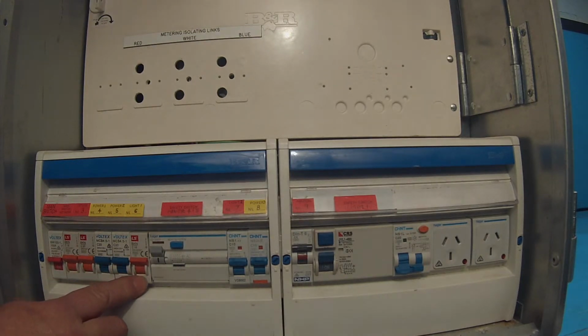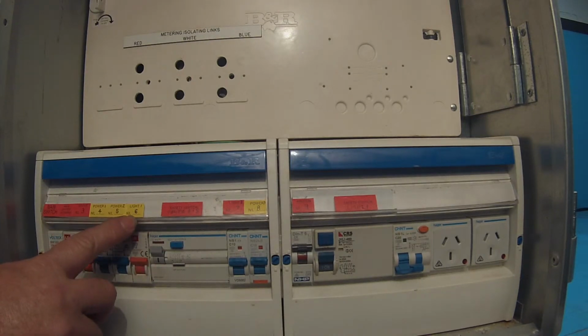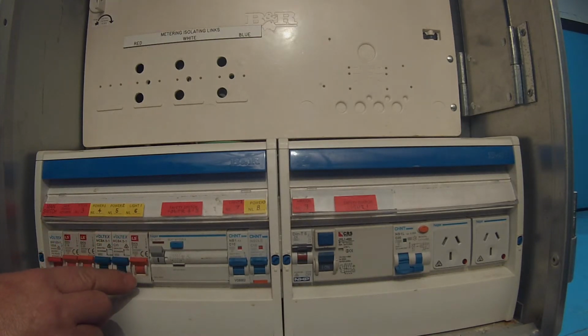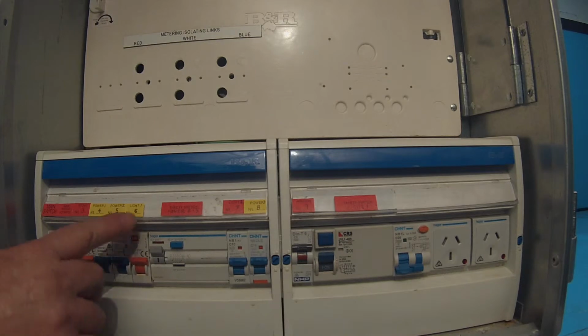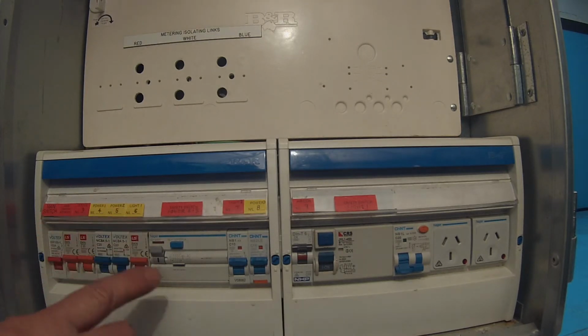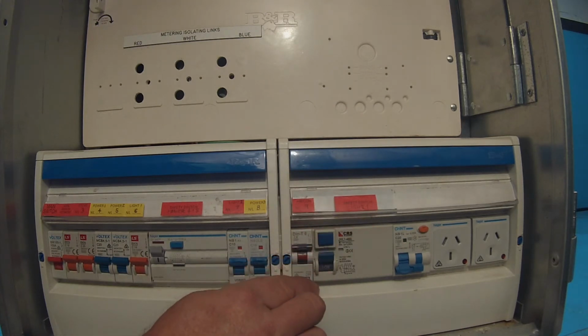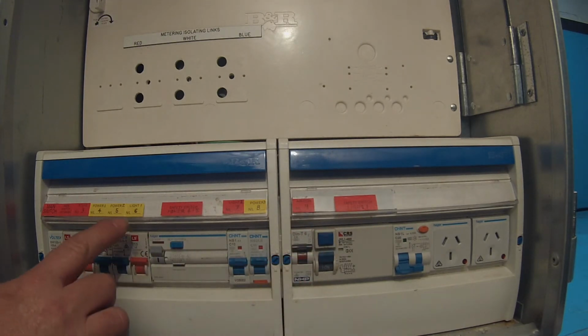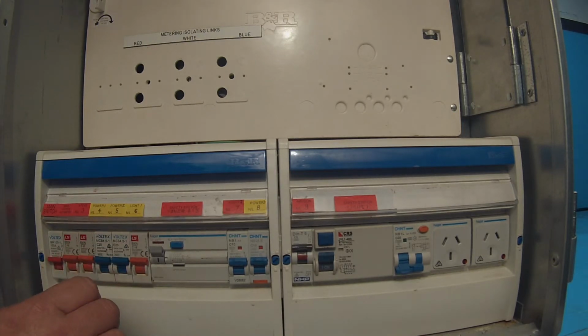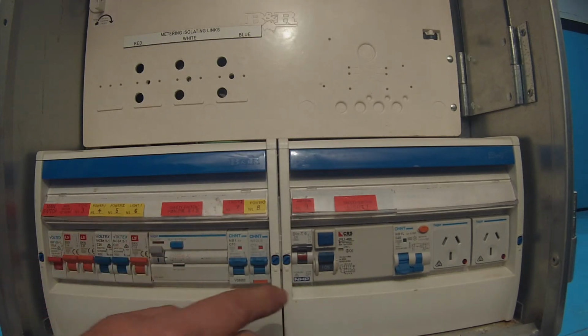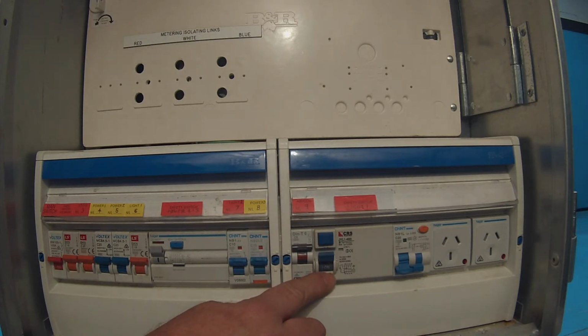The third one along here we've got is called light 1. This is a circuit breaker because it doesn't have a test switch on it, and we see that it's got a yellow tag on it again, like the power circuits do. That means that it's protected by a safety switch. The safety switch associated with it - we can look along and see that light 1 is a circuit breaker, and over here we've got the light 1 safety switch. So this safety switch runs through this from the circuit breaker through that safety switch. So this light circuit is protected by the safety switch.